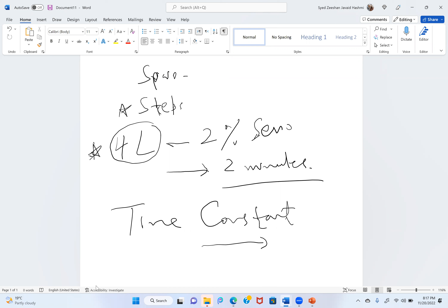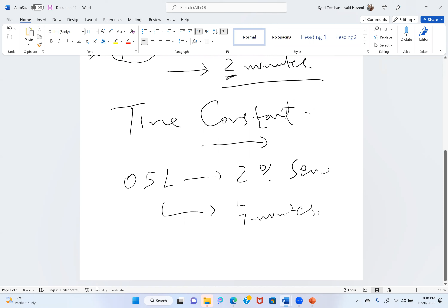Now if your flow is only 0.5 liter with the same 2% sevoflurane, you will take at least 3 to 4 times more time. For example, if it takes 2 minutes here, maybe you will take around 7 to 8 minutes to achieve the desired result. So if you open with low flow anesthesia initially, maybe the depth of anesthesia will not be achieved. So you should know that whenever we perform low flow anesthesia, we initially prime the circuit with slightly high flow.